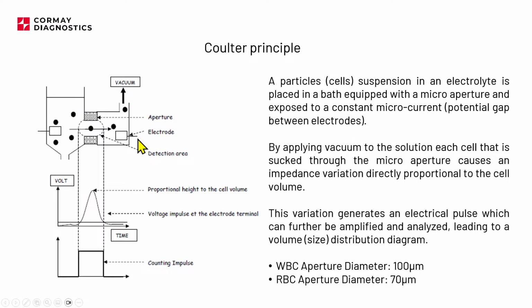And the current is also constant, right? So this whole circuit is not changing. And what will happen if we apply vacuum on this side of the aperture? We will basically draw the liquid which is in the chamber with those particles through the aperture. And when the cell is passing through the aperture, we are displacing a little bit of liquid from this exact point or this exact passage through the aperture.